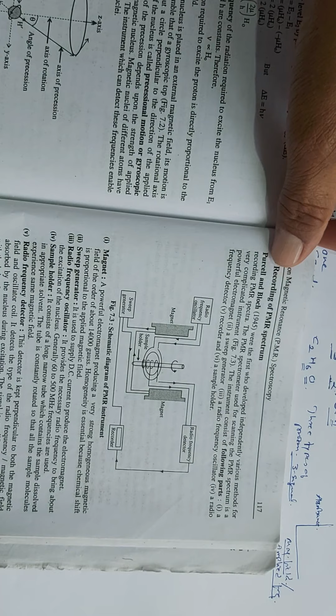Here, this dotted square is indicating the magnet. It's a strong, powerful magnet, which creates a homogeneous magnetic field applied to this sample container. So this is the sample container, the sample holder, the tube which is being used. It's a long narrow tube containing the dissolved sample.